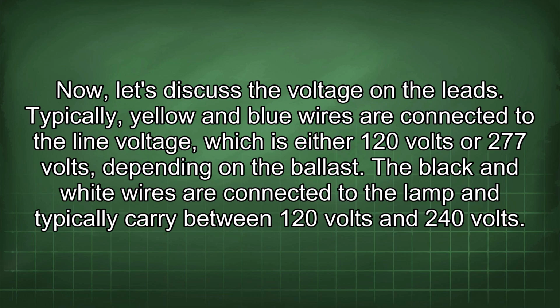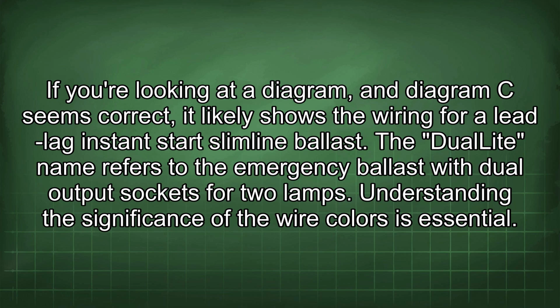240 volts. If you're looking at a diagram, and diagram C seems correct, it likely shows the wiring for a lead lag instant start slimline ballast. The dual light name refers to the emergency ballast with dual output sockets for two lamps. Understanding the significance of the wire colors is essential.